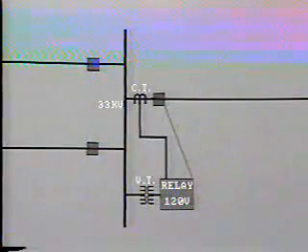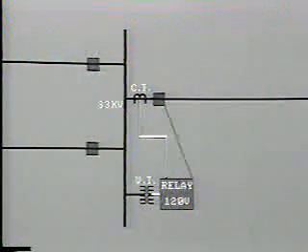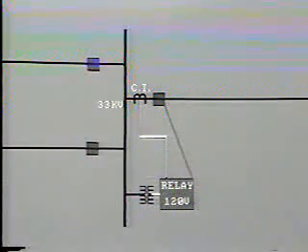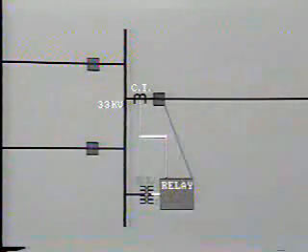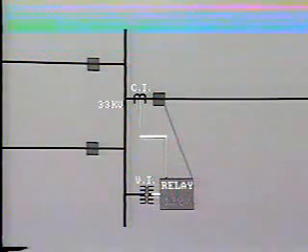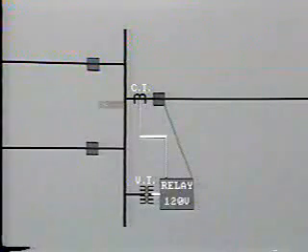However, let's return to the thrust of this program, that is, protective relaying of the power system. This circuit shows the elements of a very basic protection scheme. The inputs to the relays are provided by current and voltage. The voltage is measured by a voltage transformer connected to the bus, which may be at, say, 33 kV. The secondary side of the voltage transformer, or potential transformer as they are often called, delivers 120 volts to the relay. This voltage will, of course, rise or fall in proportion to variations in the bus voltage, so it will represent the actual bus voltage to the relay.